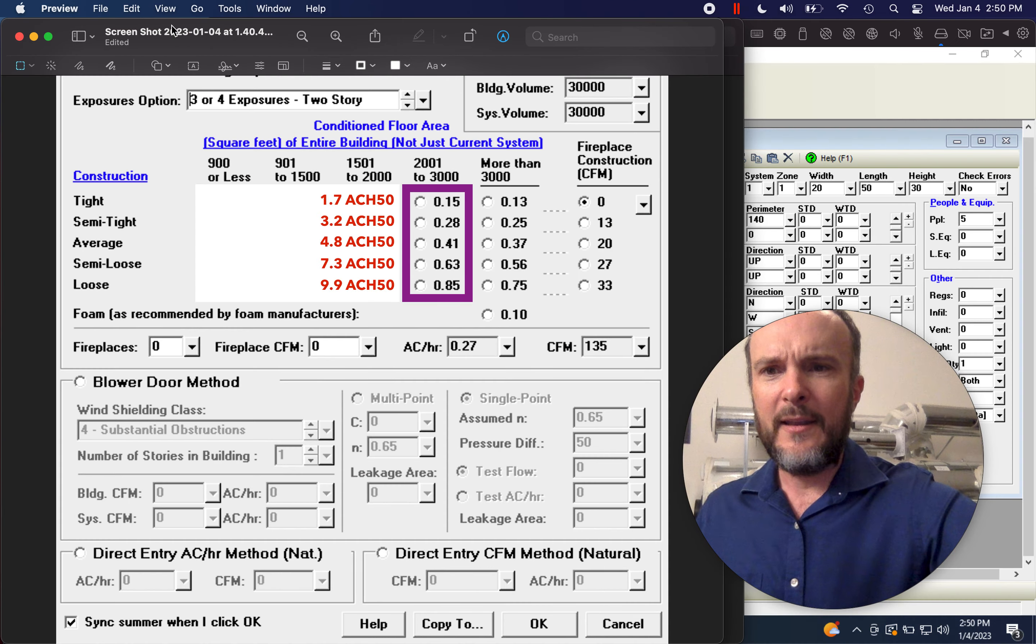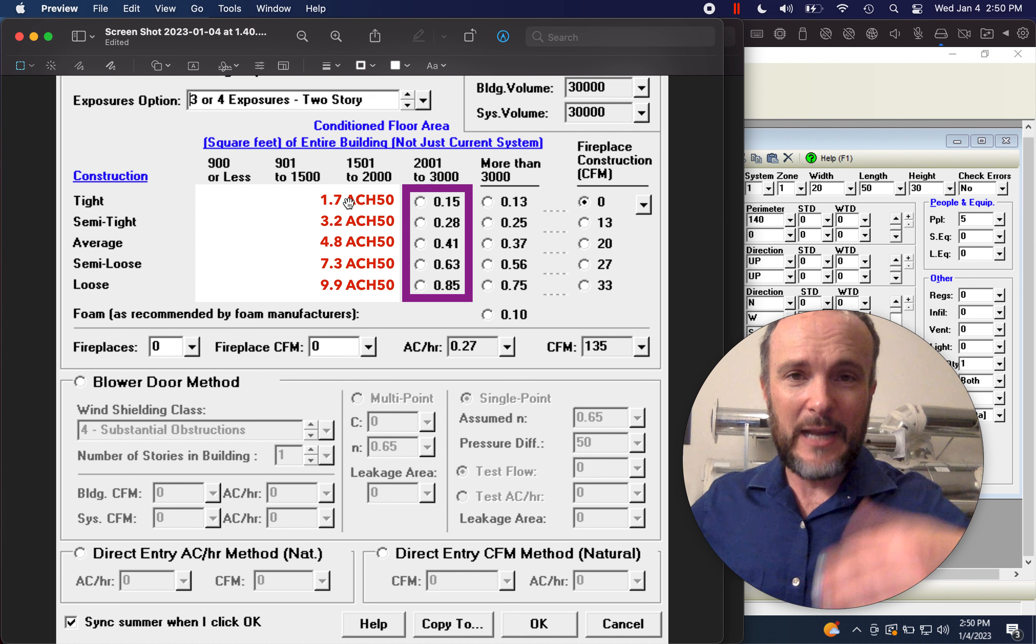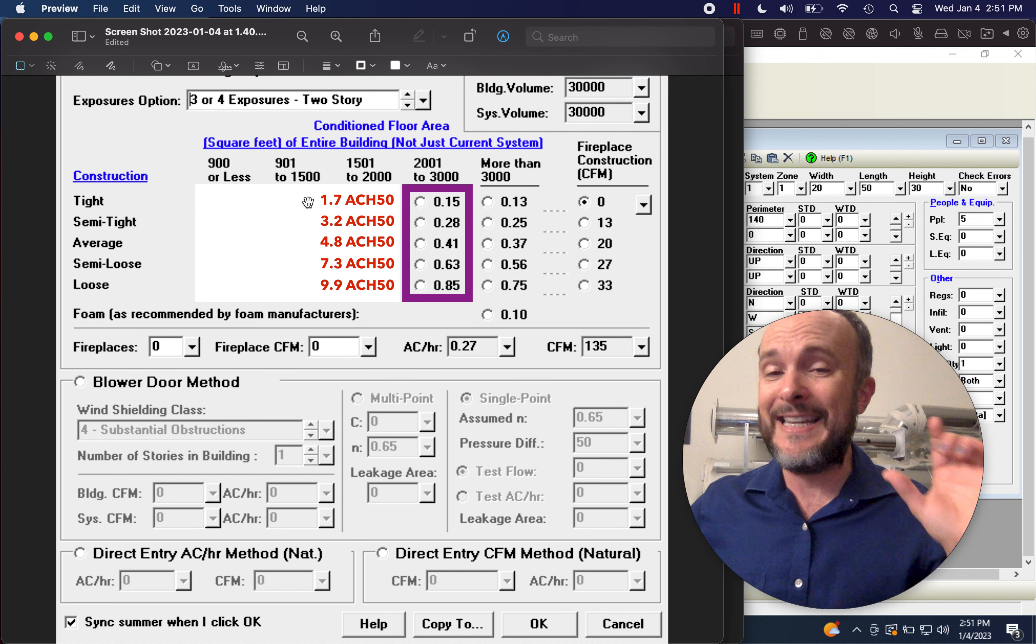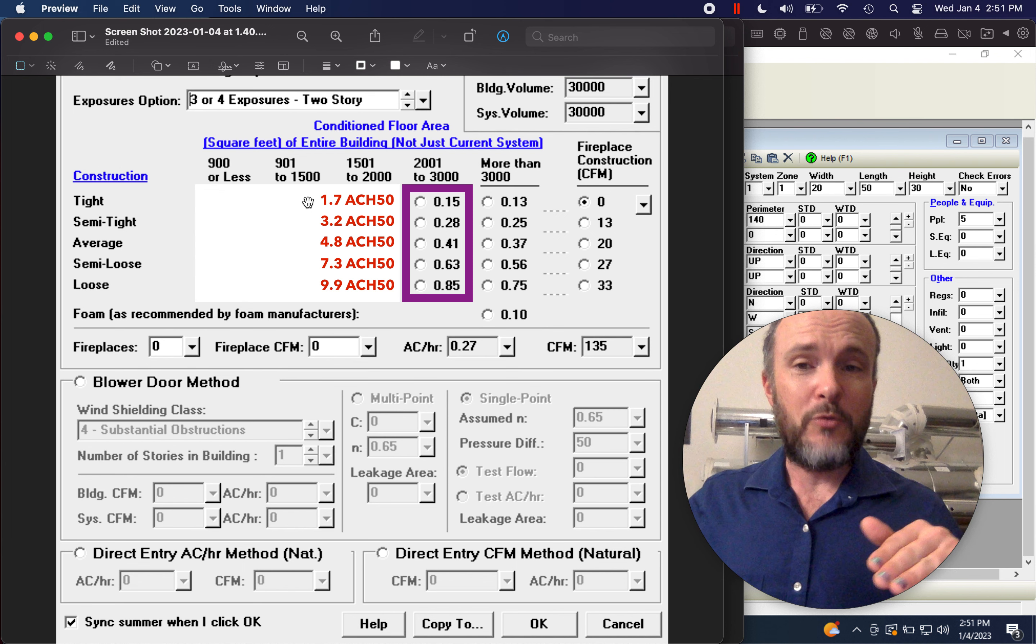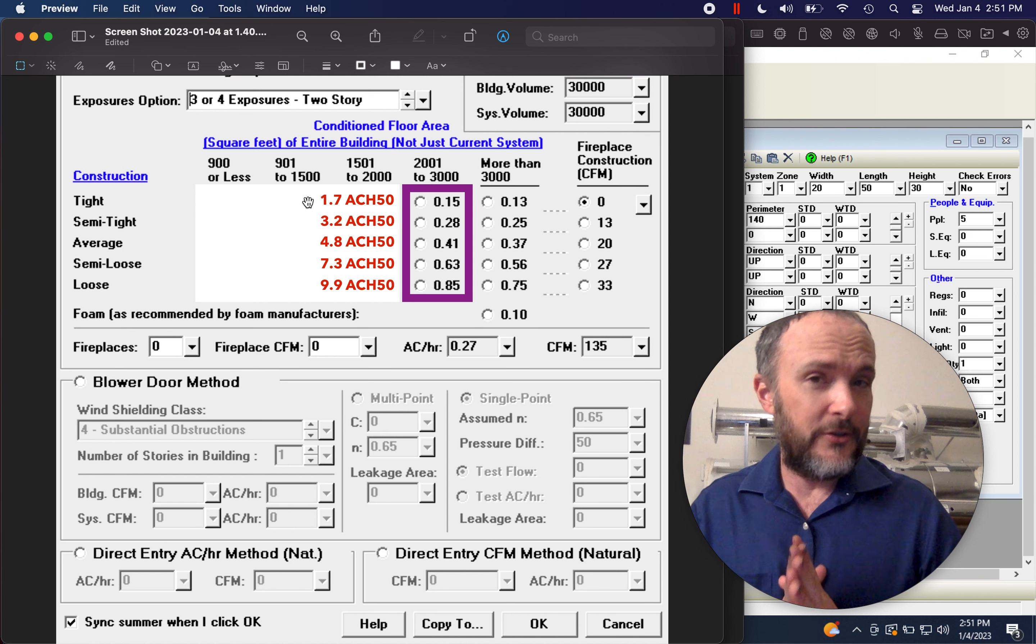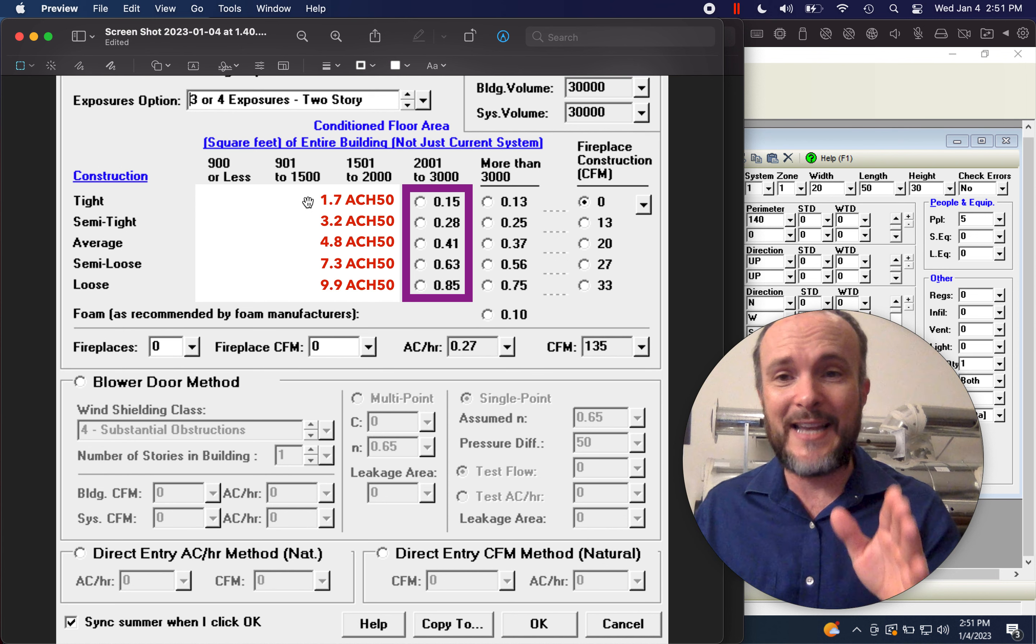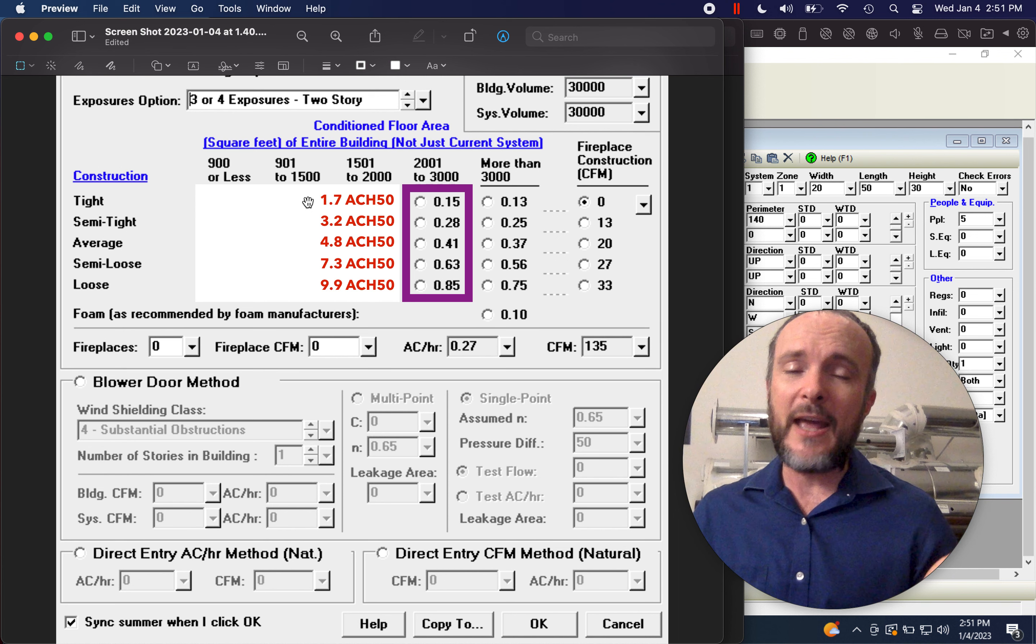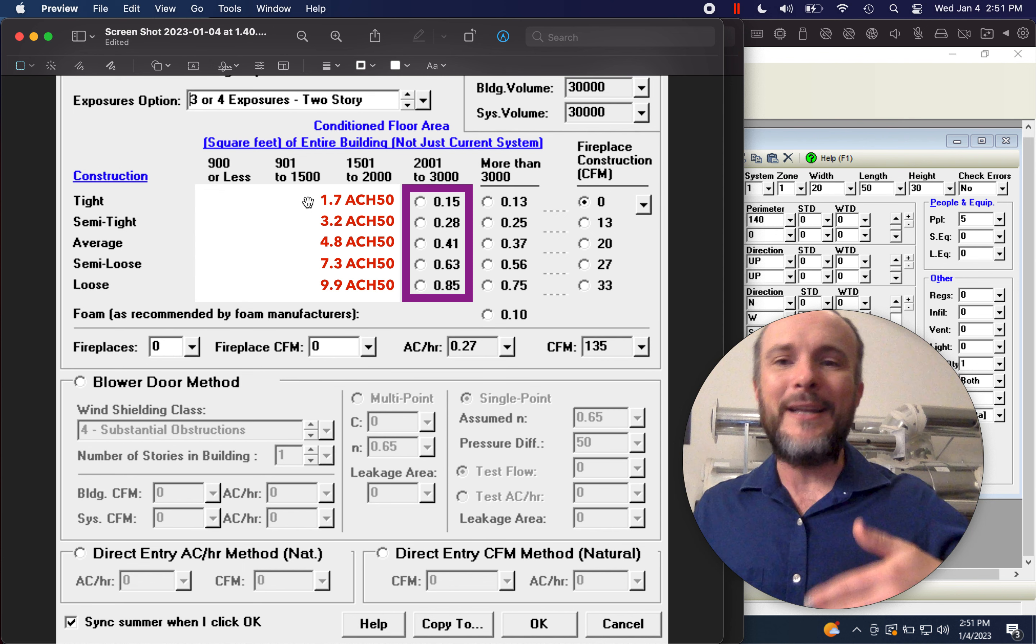That is called passive house airtight. My home that I'm talking to you from is passive house airtight. And I'm linking a video so that you can see the blower door test on my own house. But those numbers are actually not represented in this manual J air changes per hour. I'm going to show you here. I kind of broke this out. So we've got, if you look at, we've got this 3000 square foot home and we've got tight, semi-tight average, semi-loose and loose. What these really equal out to after having explored this for about an hour is 1.7 ACH 50 is the beginning. That's the tightest you can do on this default table.